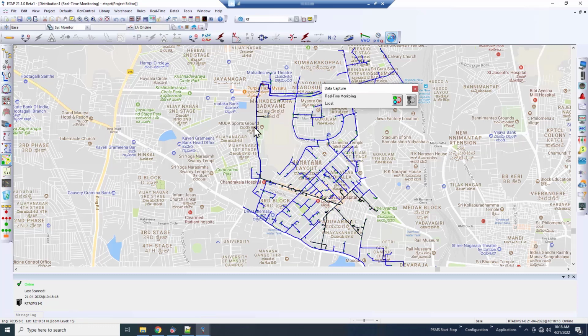So you should see it goes to de-energize. That's why it goes to black. And we should predict this top section here once the calculation comes in. So we're predicting that the fault is somewhere up here, and that is because we don't have any inputs from the fault indicators.